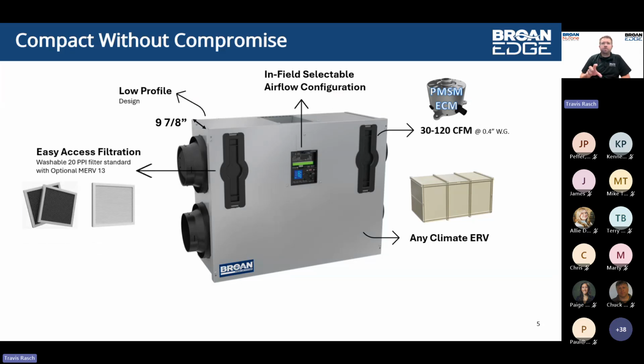Filtration. You do see maybe something a little bit unique to other products, whether it's ours or others out in the market. You see those two black, what we're calling filter access doors. Behind those access doors in the door panel are filtration. The unit comes with washable 20 PPI filters, and it also has the ability to install an optional MERV 13 filter if you need a little bit higher level of filtration for that outside air.